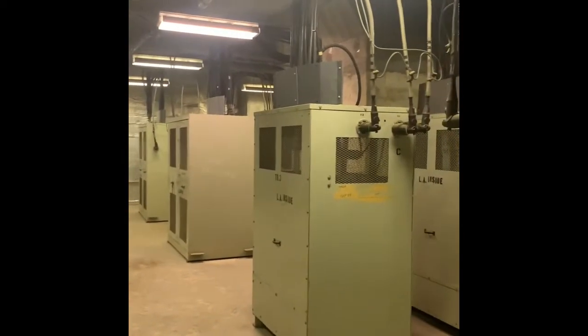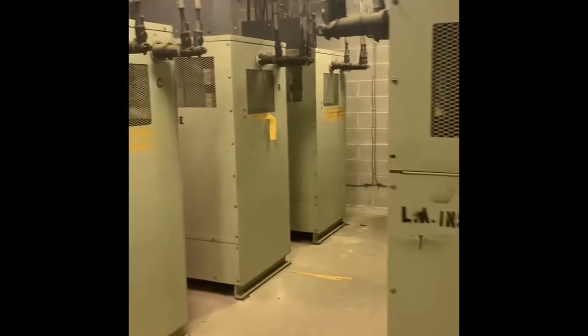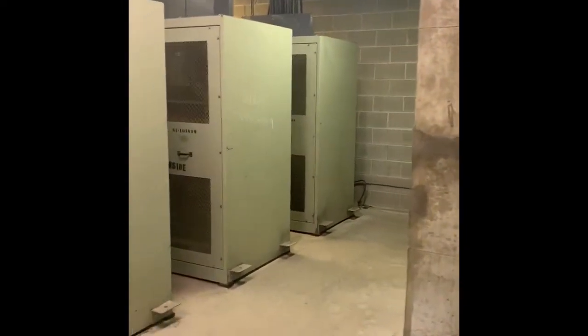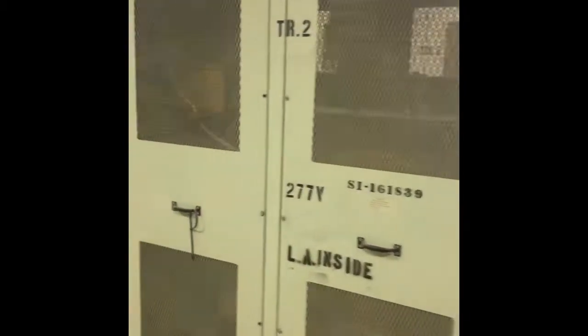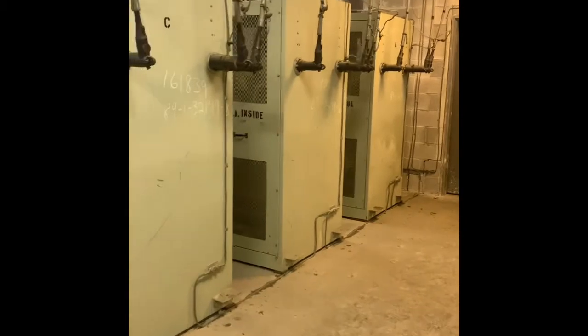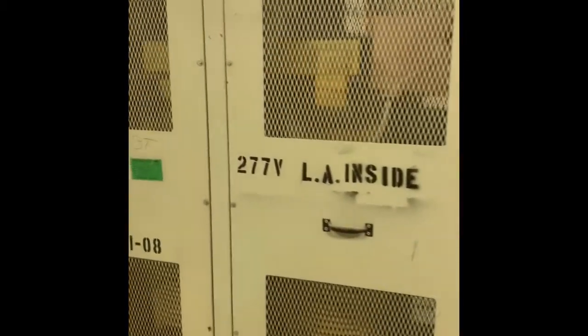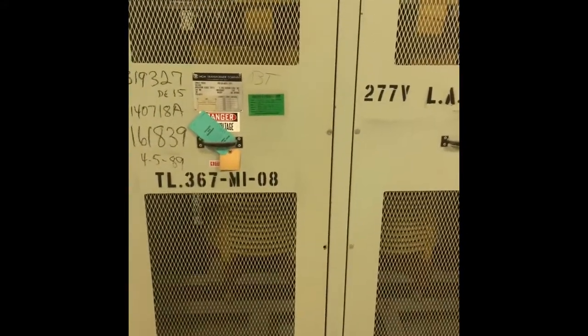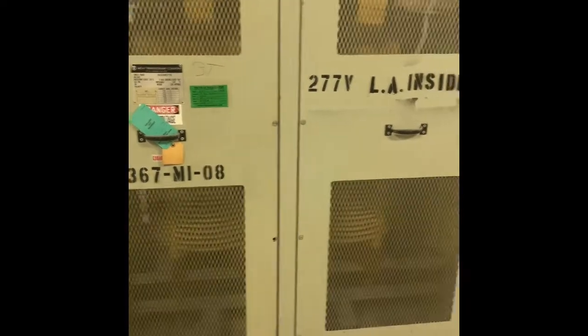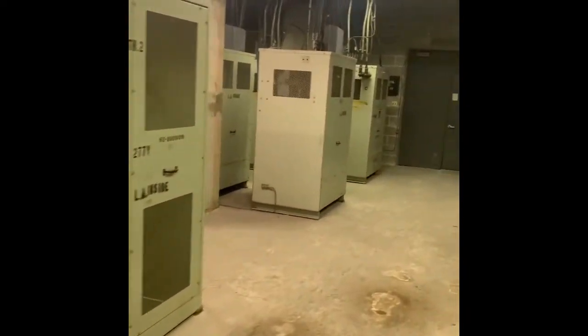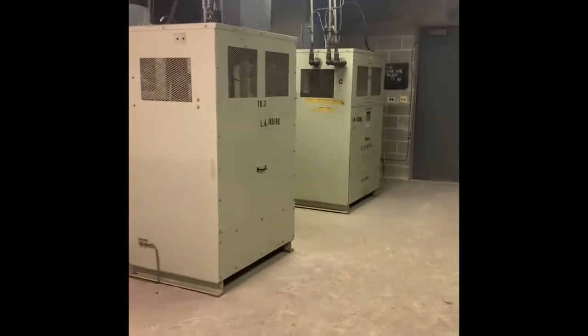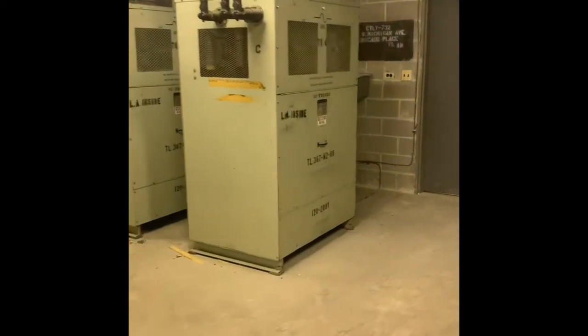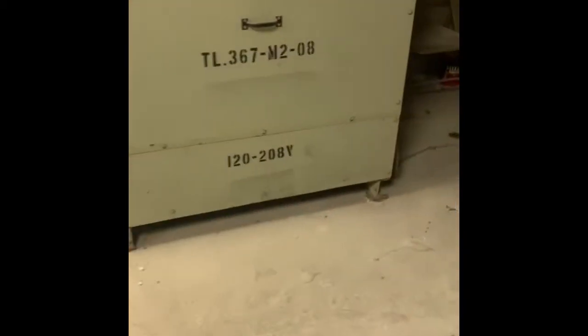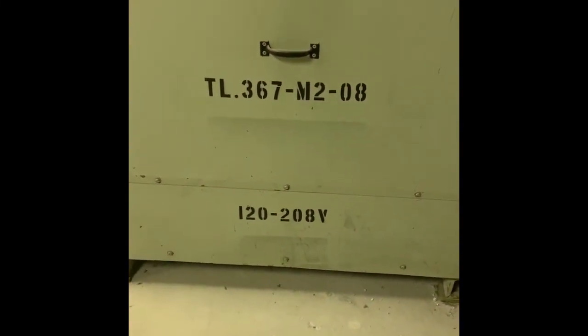From there, it goes to these transformers. So there are rows of transformers in here that are able to step down the voltage to whatever is necessary or what is required. Here we got a lot of 277 volts, so that would be the high leg Y configured transformer. This way we've also got Y configured transformers in low leg for all of our 120/208 volt requirements.